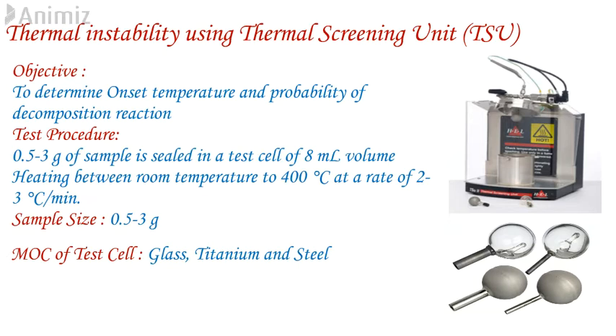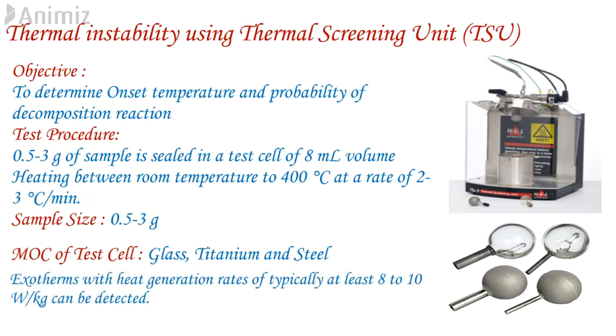Any heat generation — i.e., exotherm — or heat absorption — i.e., endotherm — is observed as a deviation from the baseline. Exotherms with a heat generation rate of typically at least 8 to 10 Watts per kg can be detected.